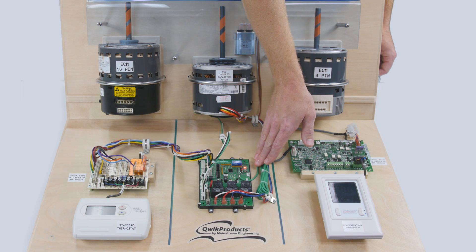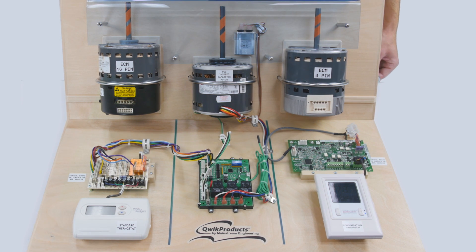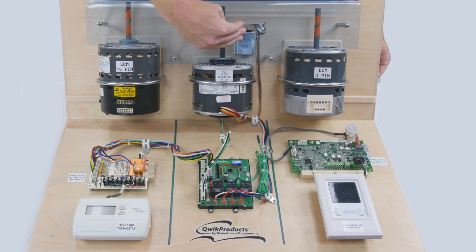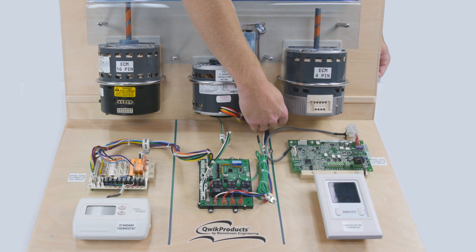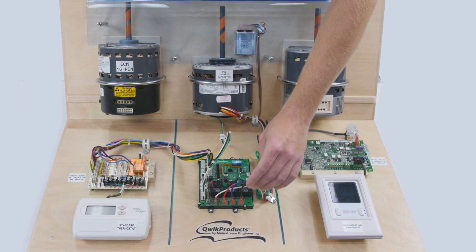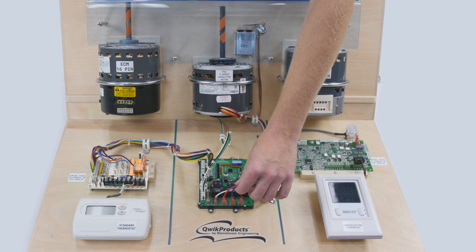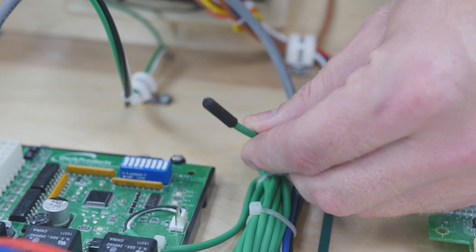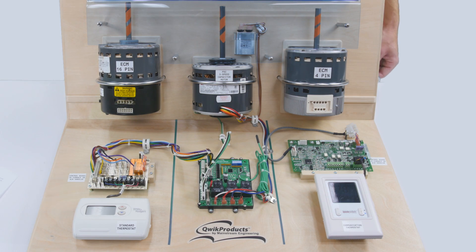After verifying that the red light stays on, turn the power back off, install the three-speed PSC motor and capacitor, wire the speed wires from the motor back to the QwikSwap V3 — high, medium, low, and common — and install the temperature sensor on the evaporator coil. Apply power and check to make sure that the motor operates properly.